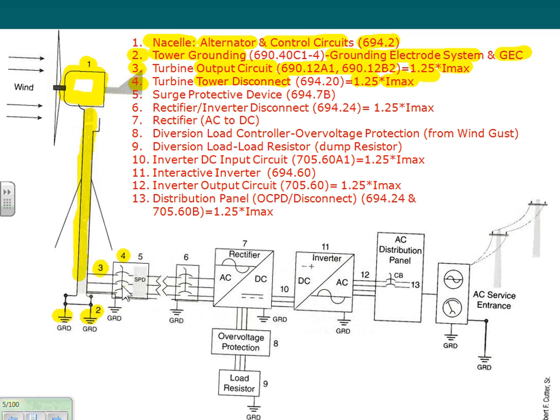And the other thing, speaking of which, a very important thing: how can you stop that turbine? Because you do maintenance on it. What the code says about stopping the turbine is that you have to have some type of direction right at the tower that explains to the technician the mechanism for bringing that turbine to a halt. It could be mechanical braking, or it could be electrical braking. So that's a requirement by code. You have to have some type of label right on the tower.